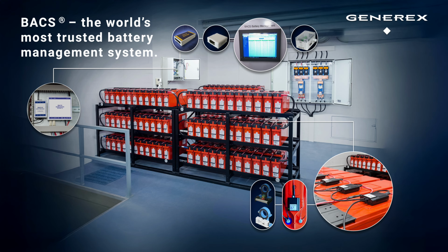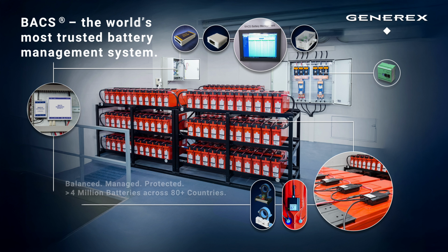The small front surface and high packing density of the batteries allow a battery service technician to perform visual checks only to a limited extent, so that a BMS is considered the only sensible monitoring for such batteries, especially when these batteries are installed in closed cabinets, as is common in the USA.